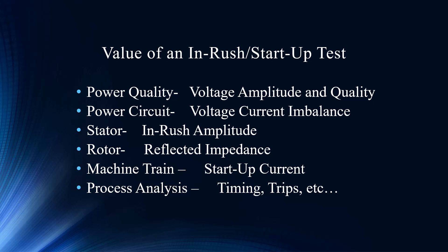I do love machine train. We've had machine train tracking using in-rush on motors and windings — on the other end of a synchronous motor, we had a machine train fault on a turning table creating an anomaly that we could see. The influence passes through to current and we love the in-rush for that. Finally, this case study is a process analysis indication — it was basically operator error, or oversight. We may have simply forgotten to clean it out, or it was a product they didn't think required that type of cleaning.